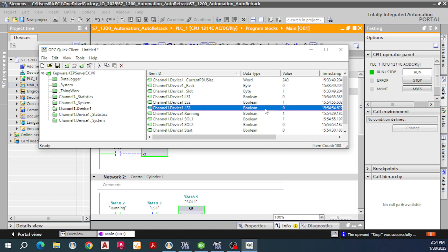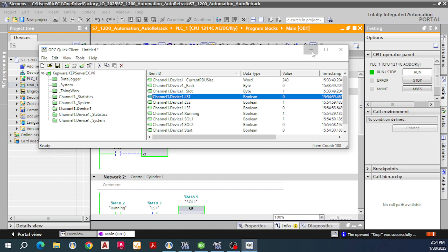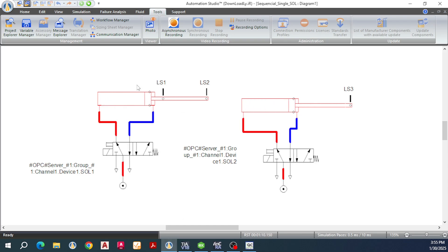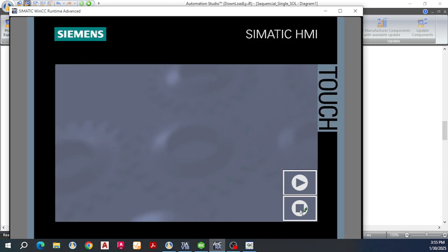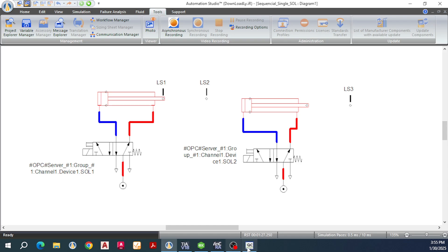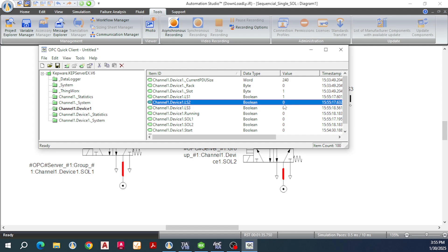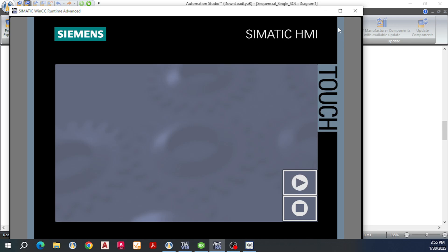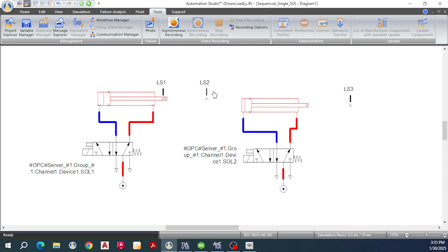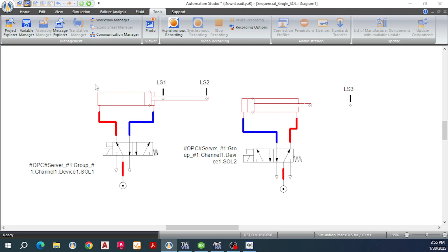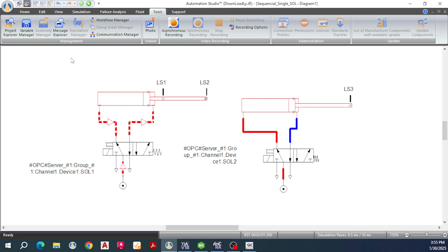The same for limit switch one, two, and three — they are switching on and off. Looking at Automation Studio, the pistons will sequentially extend and then retract. I can stop the system by clicking Stop, and the system will hold and stop. Looking at the OPC, the values are now false — solenoid one and two are false. If I click Start again, the pistons will sequentially extend and retract. This is how to connect the Siemens S7-1200 PLC into Automation Studio.